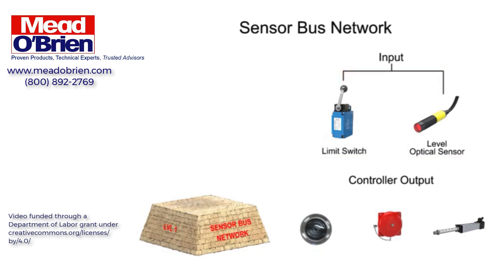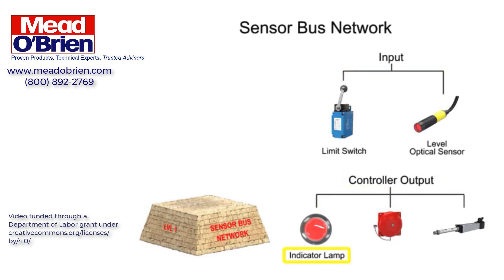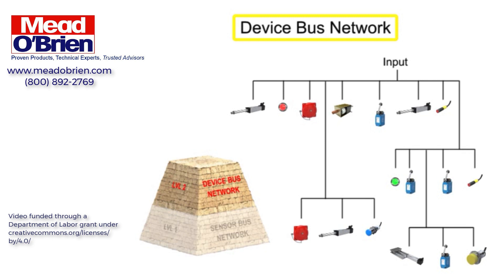multiple basic field devices like limit switches or level optical sensors are connected to one network cable. The sensor bus network is also capable of transmitting output signals from the controller over one cable to indicator lamps, alarms, or other actuator devices. The next increasingly complex level of industrial field bus networking is the device bus network.